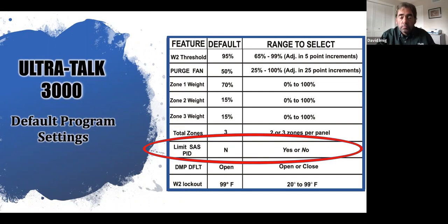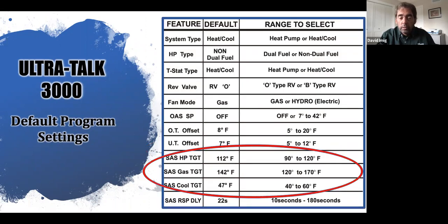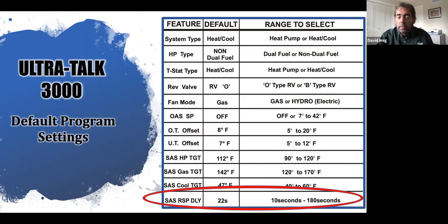So in review, remember we selected no. We're going to allow this PID loop to help us operate and stage this particular equipment. If we look at our target temps, 112, 142, 47, these are temperatures we're looking for in the supply plenum to satisfy the calls in their particular areas.